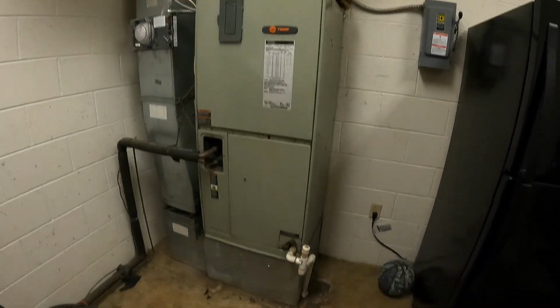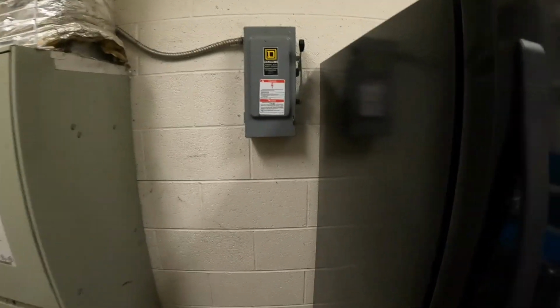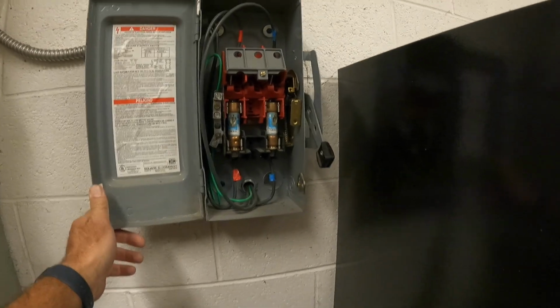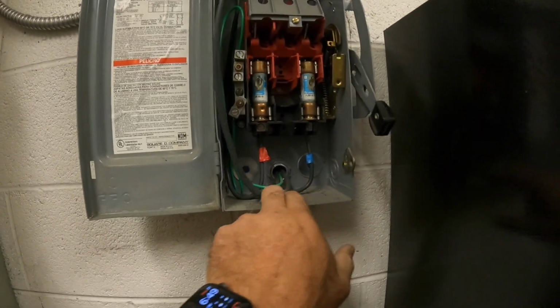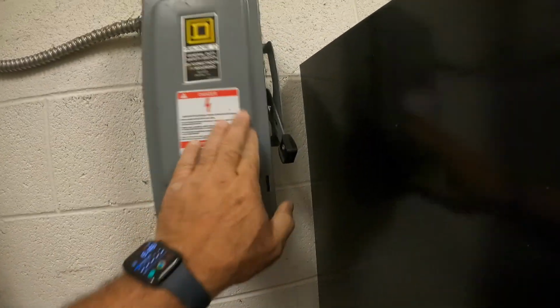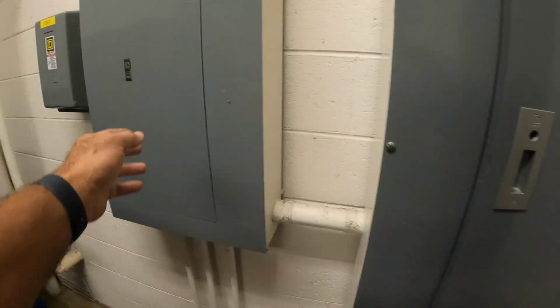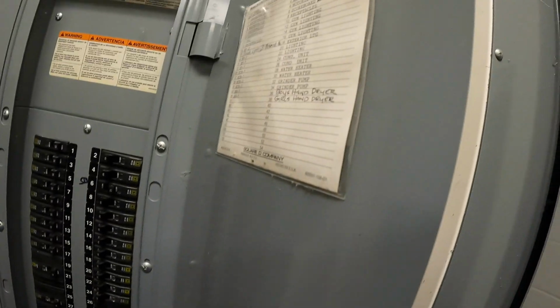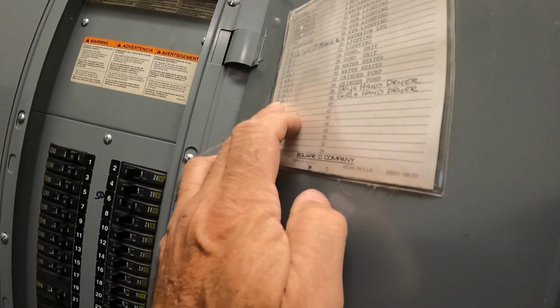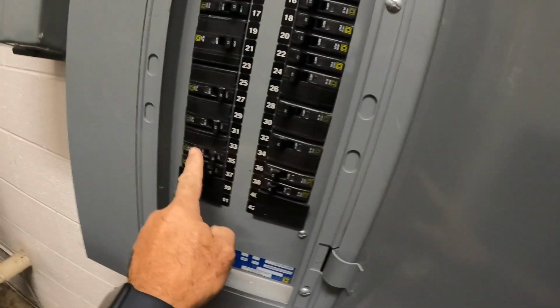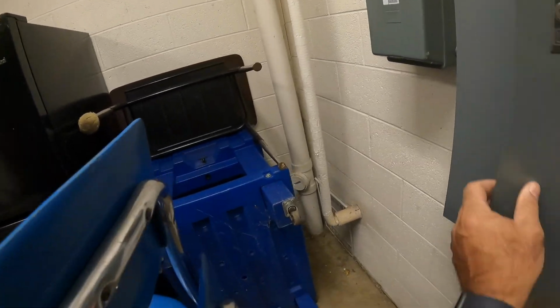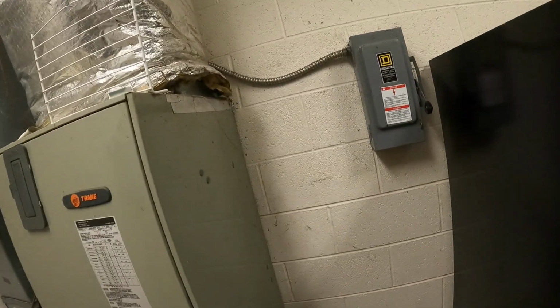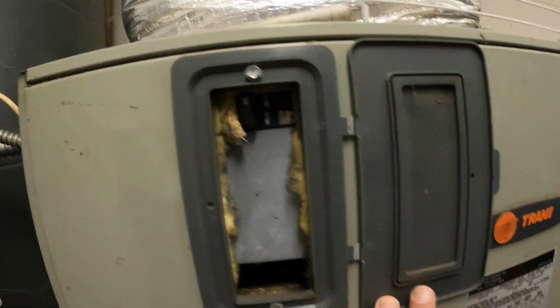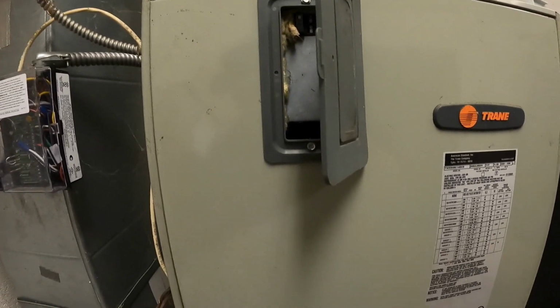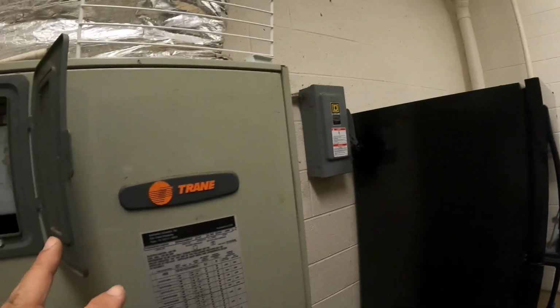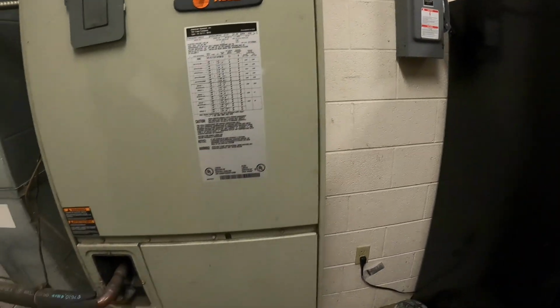While we're waiting on daylight so we can see where we're at outside, let's get a look at this and see what we're going to be involved in. You can see it's single phase. We only have 2 lines coming in, 2 fuses. It's got 60 amp fuses here. However, condensing unit, air handler. We have a 50 amp breaker, so that's really just a disconnect in there. Those 60 amp fuses would be just like 2 pieces of copper. Got a 60 amp breaker in here. Hopefully it's got an 8 kW heat kit, because that's what I ordered. Can't put more than that on a 50, especially with these new ECM motors.